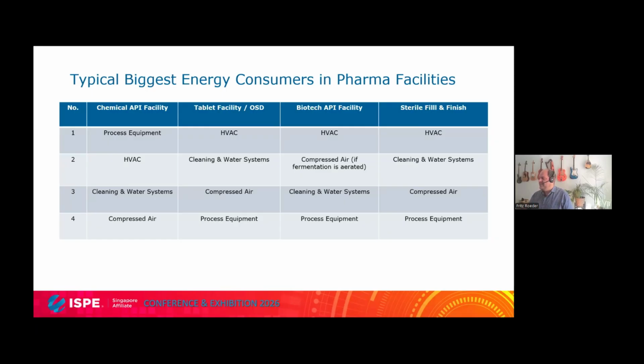I can tell you, we've updated an ISPE guide 2 years ago, rewriting specifications, because that was always a problem in practice: how can you set a proper specification for compressed air and gases? There's this nice ISO standard 8573, which is pretty common, but it only defines classes. It doesn't tell you as a pharma company what the right class is for you, so you can't basically use it as-is. You can use classes, but you need to define your own spec risk-based. That's why we've updated the ISPE guide on gases, to give people some info and guidance on what makes sense. I'm going to show some nice examples later.